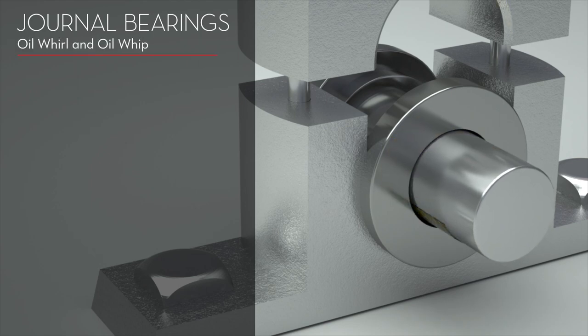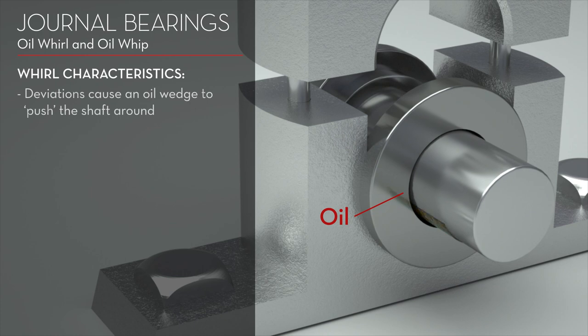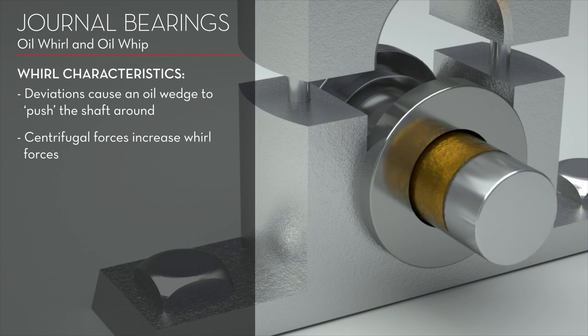Oil Whirl is an oil film-excited vibration where deviations in operating conditions cause an oil wedge to push the shaft around within the bearing. Instability is introduced through higher centrifugal forces, which increase whirl forces.